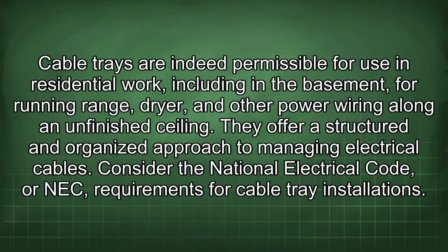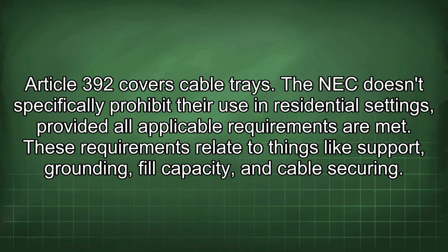Cable trays are indeed permissible for use in residential work, including in the basement, for running range, dryer, and other power wiring along an unfinished ceiling. They offer a structured and organized approach to managing electrical cables. Consider the National Electrical Code, or NEC, requirements for cable tray installations. Article 392 covers cable trays.